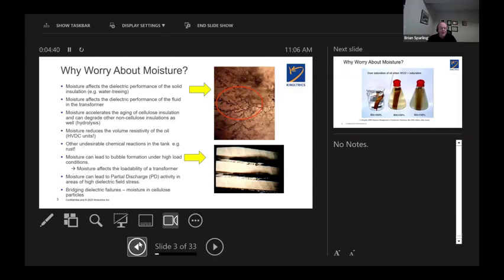But moisture reduces the volume resistivity in the oil, and this is particularly concerning when you're looking at HVDC transformers. This is a key item of interest for those people with that, is the resistivity of the oil in the DC transformers. The other thing is that water can have an undesirable other chemical reaction inside, like rust. Everybody thinks, we have water, metal and rust, and it's oil. It's never going to rust. Well, it does. You have iron. If you think of the equation, Fe, which is iron, plus H2O, the O transfers to the Fe, that's ferrous oxide, rust, and you're left with hydrogen. So it's a chemical reaction.